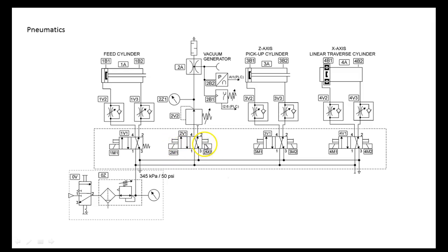It's dual solenoid, right? Four way, four port. This solenoid actuates and pushes that direction, and what you have to do on these symbols is visualize this whole thing moving. So when this one actuates, it's going to take this block and push it over here. So now pressure, which is coming in on one, is going to go to four. If we push it in this direction, pressure would go over to two. And then we come back through exhaust.